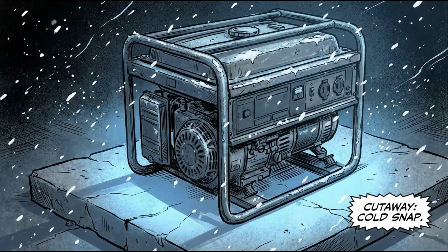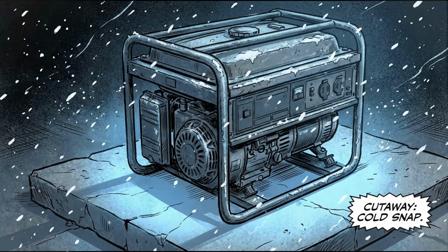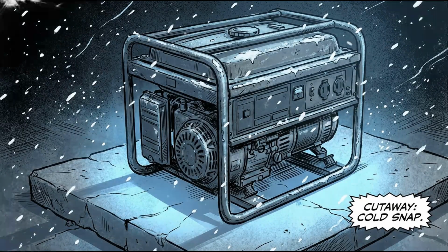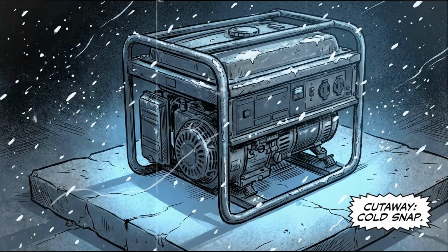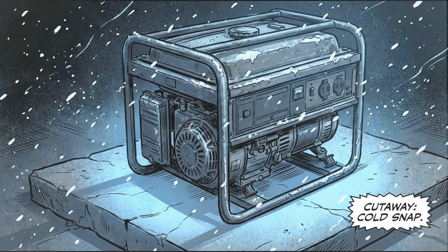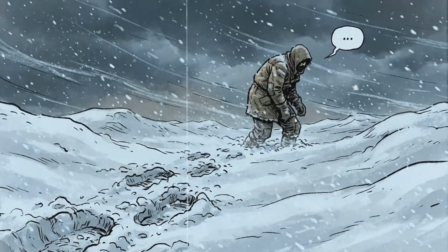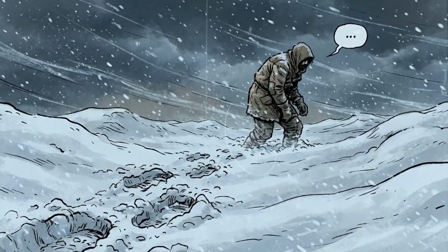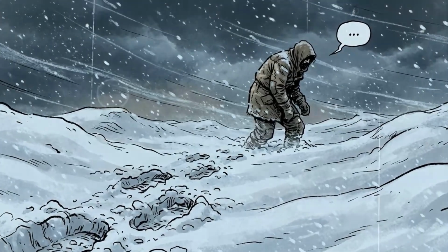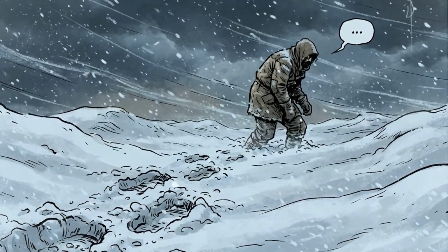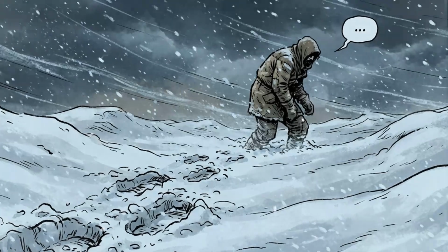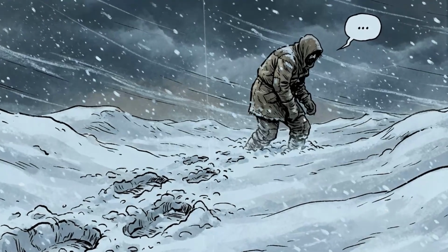The generator must be outside, a minimum of 20 feet from any door, window, or vent opening. In December, in the ice storm. This is a real operational constraint. If your plan requires someone to go outside to manage fuel and check a running generator in a winter storm, factor that into your comfort level with the plan.